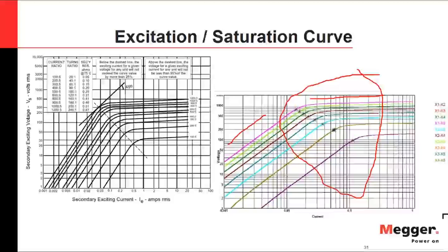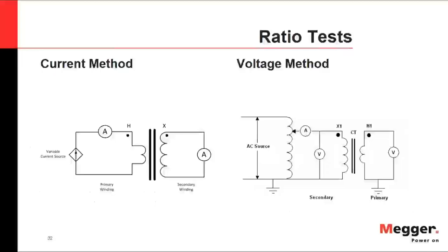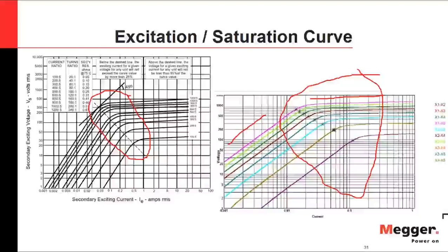Once the saturation point is known for the specific CT being tested, ratio testing can be performed on the linear zone of the response. The ratio test can be performed by two methods: the current method and the voltage method.